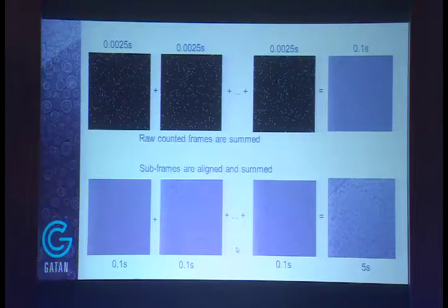Now, the signal and noise in the subframe is not terrific, but it has enough signal and noise that you can start to see the specimen in the image. And when you have enough information like this, then you can take this image and the next 1/10 of a second, and the next 1/10 of a second, and the next 1/10 of a second, and you can align these frames to each other to try and correct for drift down to about 1/10 of a second, right?